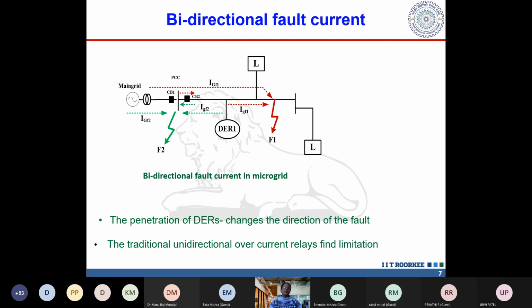Yeah, thank you. So this bidirectional fault current means, now due to the integration of renewables to the existing network, if there is some fault, then the power flow may be from any side, isn't it? Because the current is going to be contributed by the renewable sources as well, right? So for example, I have kept one example in front of you: the green one, let us say, is one fault position, the red one is another fault position, and this is my observation point. Here my cursor, you can see, this is my relay R1 observation point. For my fault F1, this grid will supply a fault current, the red dotted line, and the renewable source will also supply a fault current, the dotted line.